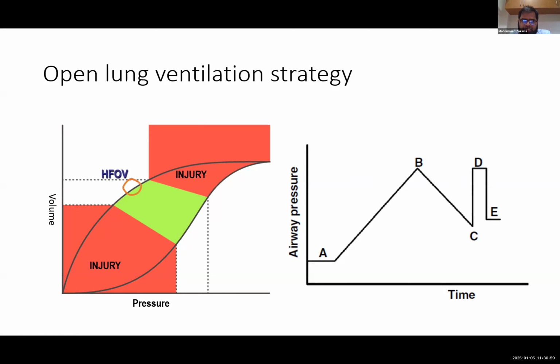But in HFO ventilation, you apply the same concept: during the inspiratory phase, when you are giving MAP and the lungs are open, you will go back onto the expiratory limb of the PV curve, and you will keep the pressures there so that lungs are adequately recruited and there is better expansion. So in HFO, you give the same pressure continuously. There won't be any swings during this cycle, and adequate delivery of the volume will happen. So this is the basic advantage of HFO.